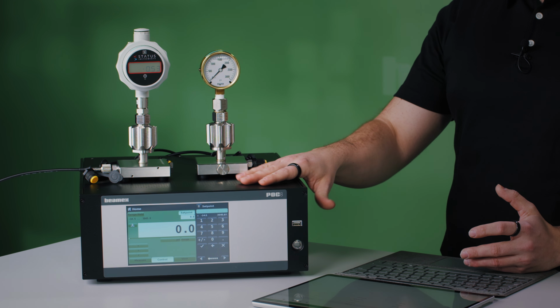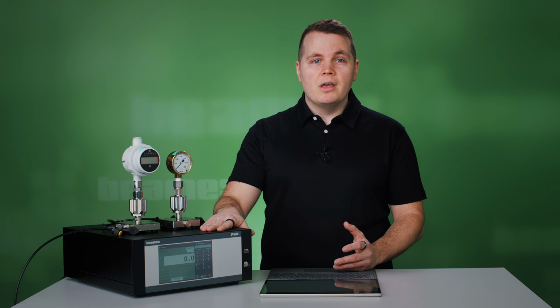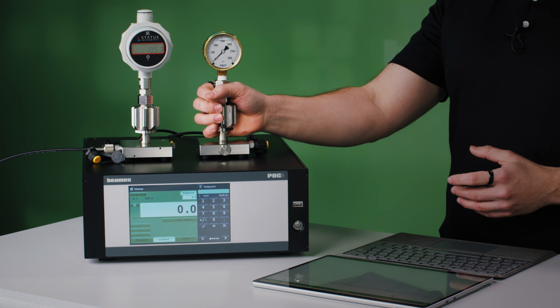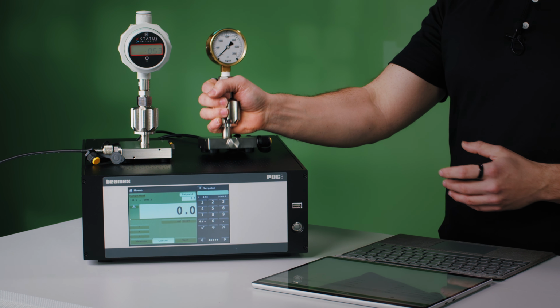I'm Ville from Beamex. I'm going to perform simultaneous calibrations using the Beamex bMobile application. Here are two pressure indicators that will be the devices under test. One is a digital and the other one is an analog indicator. The reference pressure will be controlled using the POC8, which is this big box right below. The pressure indicators are mounted on their own calibration stands, which are then connected to the POC8.